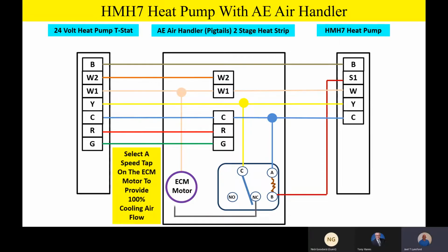The normally closed contact on the relay, we're going to swing over and select a speed tap on the motor itself. We're going to select a speed tap to give us 100% cooling airflow. And as a quick reminder, we always want to set up our ductwork so that we have our nominal airflow at 400 CFM per ton. 400 CFM per ton is the normal nominal airflow this is designed for. So if we've got a 3-ton unit sitting outside, we have to set up our ductwork and this airflow tap for 100% cooling airflow, and as an example, that would be 1,200 CFM on this normally closed contact for 100% airflow.